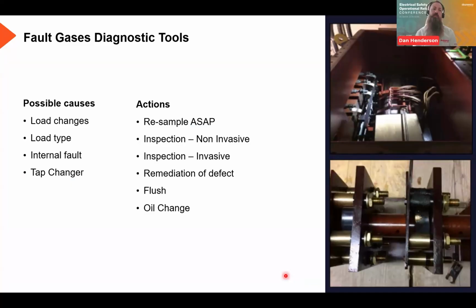No, that's fine. Just to add on to that, onto the DGA side, as Ryan mentioned, this is probably one of the most important tests that you can do to understand the asset's health. It's a really good snapshot to understand how the transformer is operating and any internal issues, and this is probably one of the most overlooked tests that I see. Often, as we've covered, you've got the fluid quality tests, then you've got your additionals, and because this is an additional, the increase in price is marginal. It doesn't matter what vendor does it, all the prices are marginal on top of that. But for whatever reason, whether it's cost or knowledge, it's always one of the most overlooked tests.